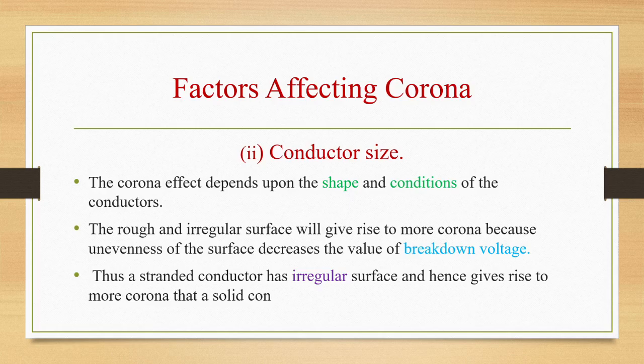So how is conductor size affecting the corona? Corona effect will depend upon the shape and condition of the conductor. A rough and irregular surface will give rise to more corona because the surface will be uneven and breakdown voltage will be decreasing. So a stranded conductor will have an irregular surface and it will give rise to more corona than a solid conductor.